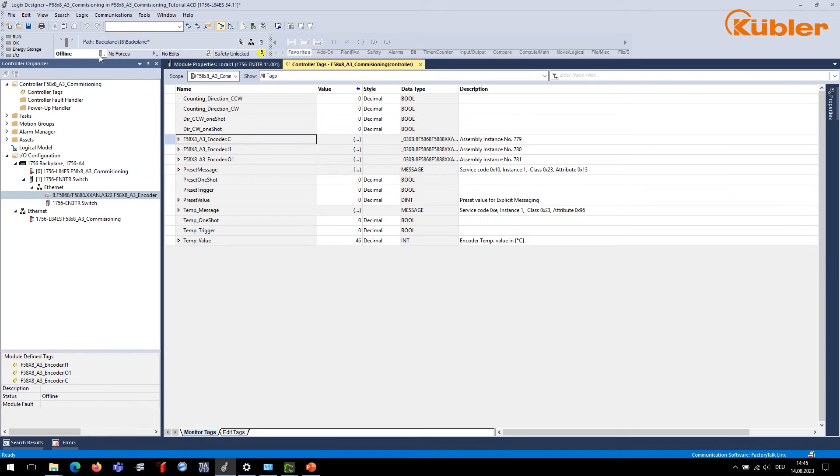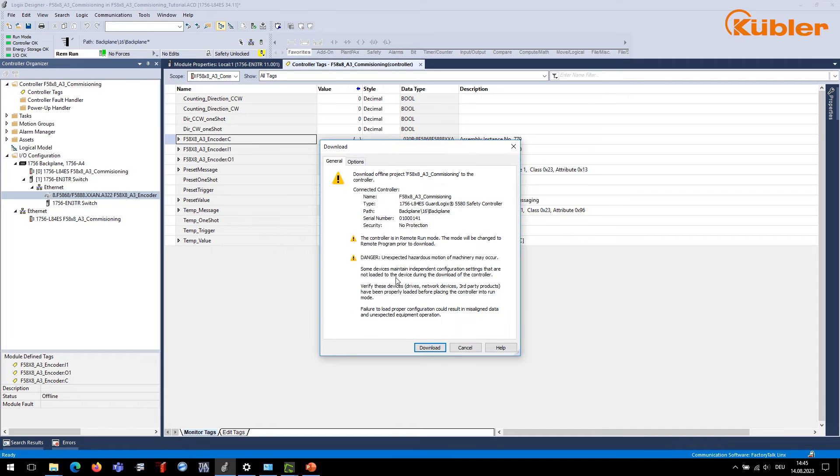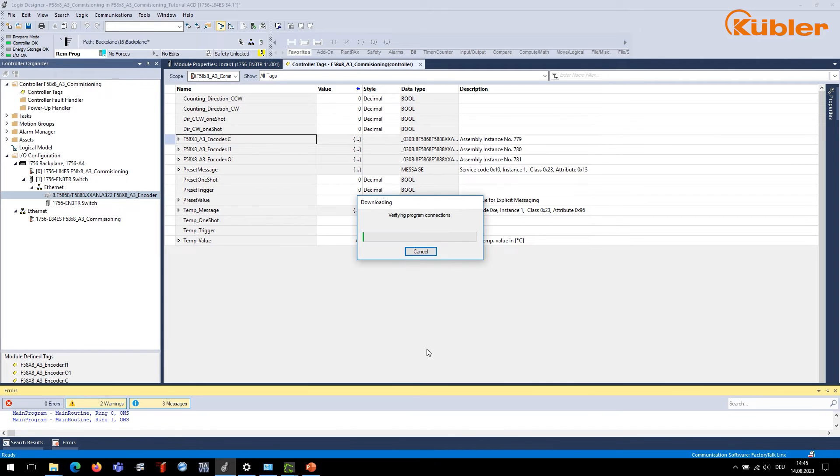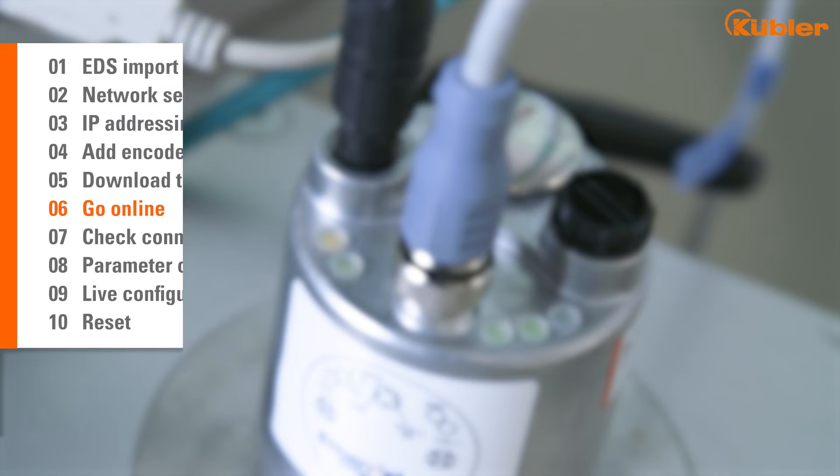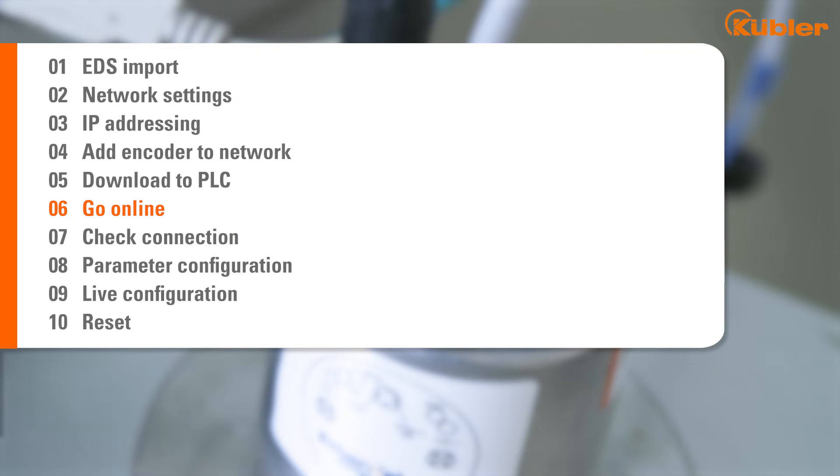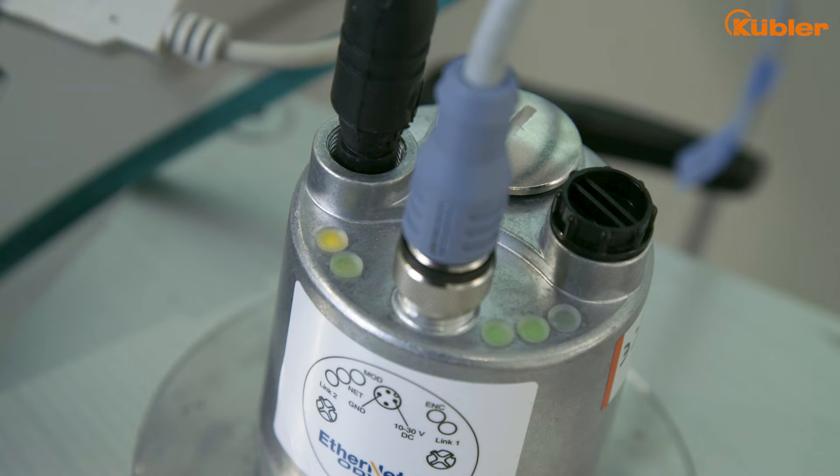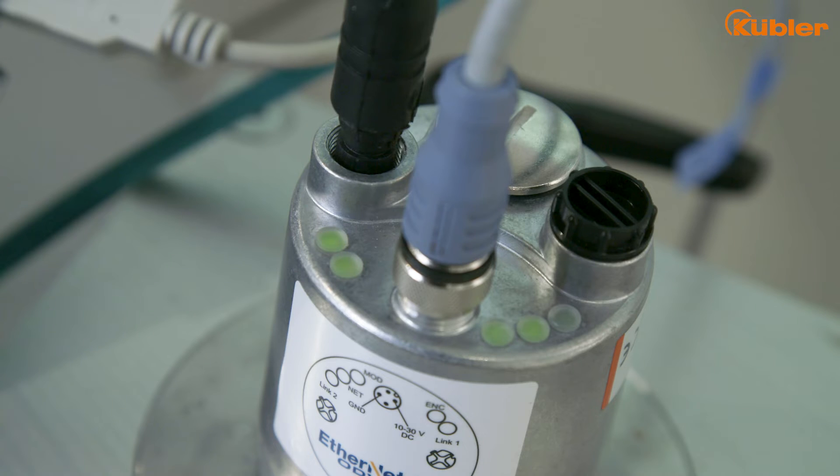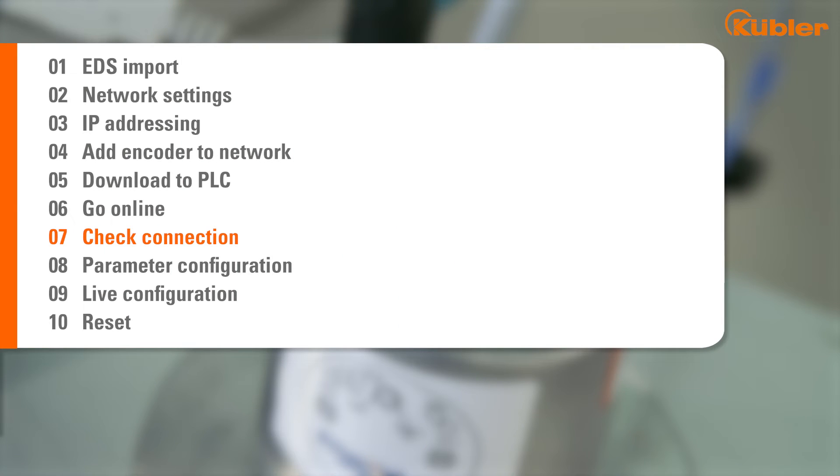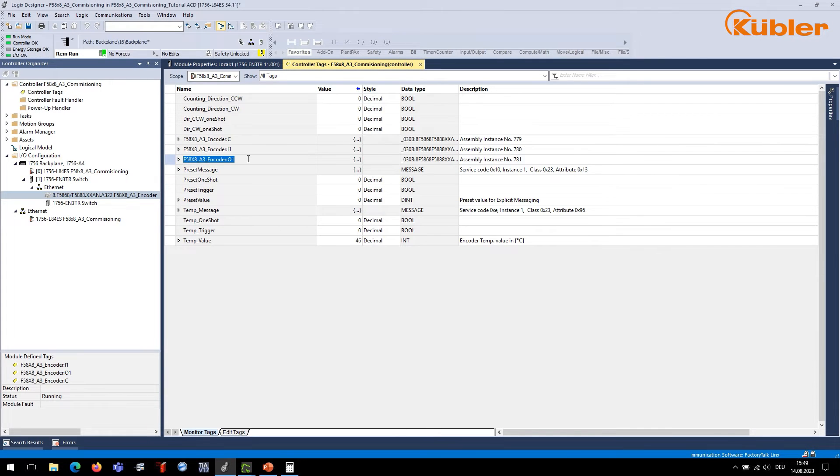Once everything is set up, you can download the configuration to check on the input values from the encoder. Click on Controller Status and choose Download. As soon as you go online, the encoder LED will turn green. The data exchange is indicated by the yellow flashing port LED. Navigate to the Controller Tags area. Here, you will find all assemblies of your connection listed beneath each other.